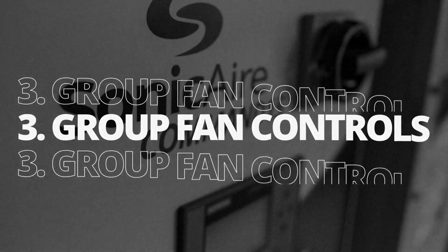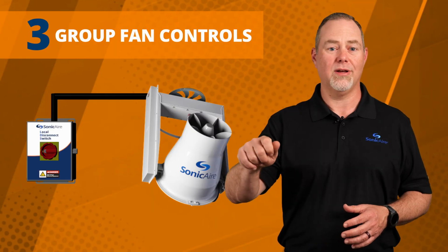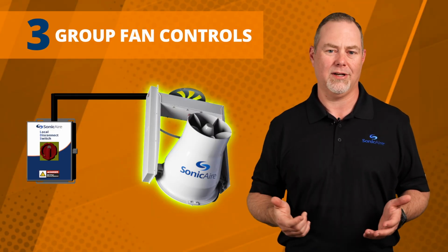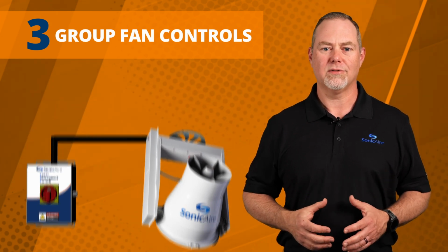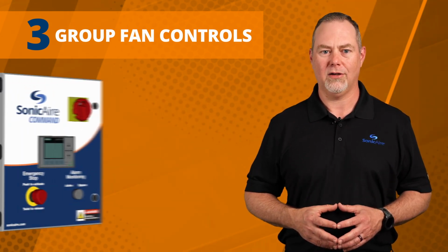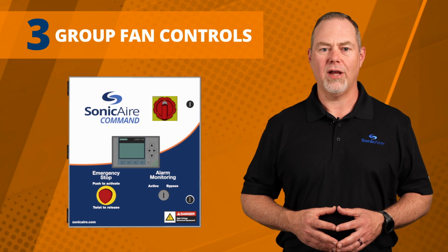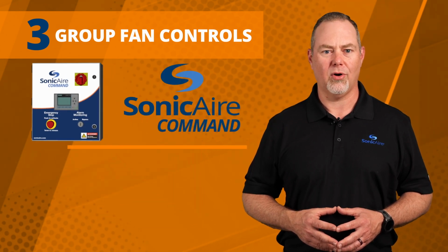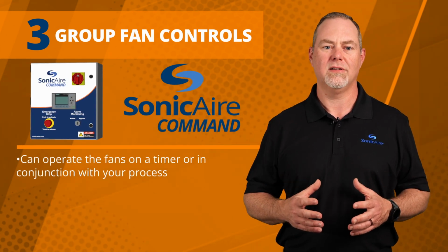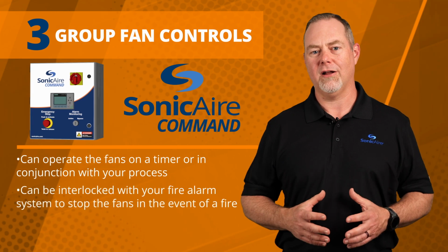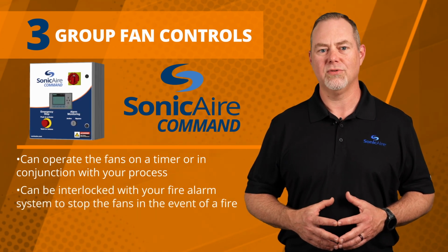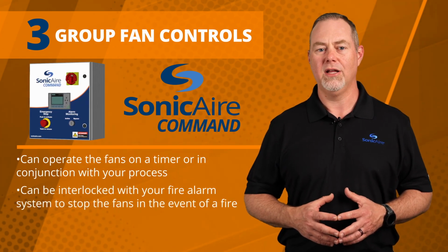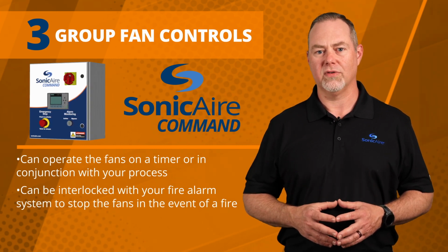Number 3, controls. Our fans can be operated as simply as manually turning them on and off with one of our local disconnect switches. However, most customers opt for our command control panel, which will operate a group of fans on a timer or in conjunction with your process. This panel will even interlock the fans with your fire alarm system to ensure that they do not operate should there be a fire event in your facility.